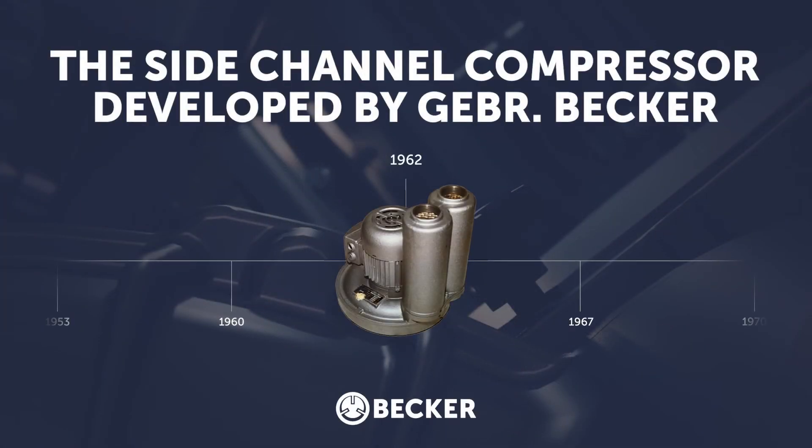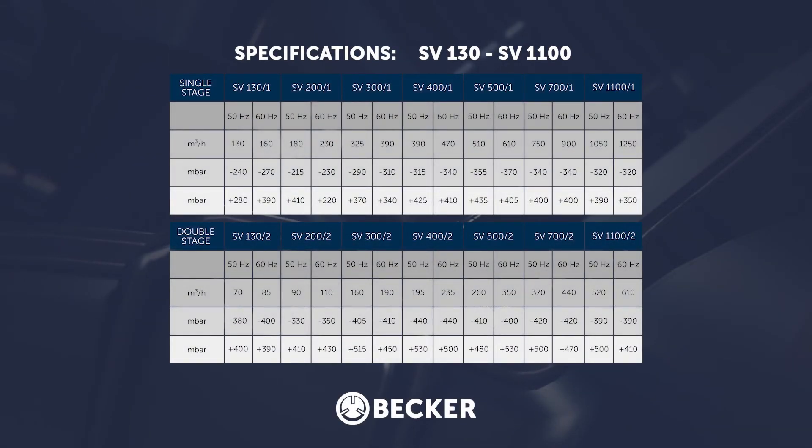Becker developed and introduced side-channel blowers more than 50 years ago. All are dry running, oilless pumps which can be used for either vacuum or pressure. For each model, there are both single and two-stage options. The two-stage allows for increased pressure or vacuum but with a decreased airflow. The range from Becker allows for flows from just over 40 metres cubed per hour to an excess of 1000 metres cubed per hour, with vacuums as high as 440 millibar relative or 500 millibar on pressure.